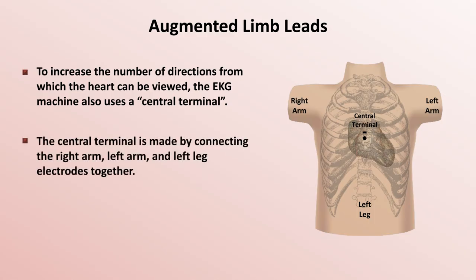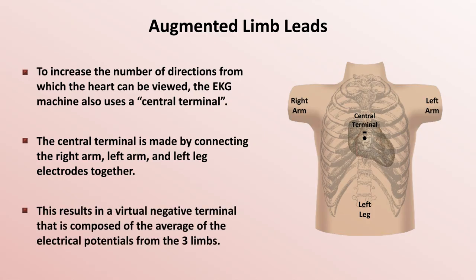As mentioned before, the central terminal is made by connecting the right arm, left arm, and left leg electrodes together. This results in a virtual negative terminal that is composed of the average of the electrical potentials from the 3 limbs.